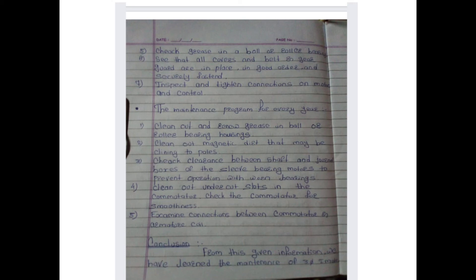The maintenance program for every year includes: first, clean out and renew grease in ball or roller bearing housing; second, clean out magnetic dirt that may be clinging to the poles; third, check clearance between shaft and journal boxes of sleeve bearing motors to prevent operation with worn bearings; fourth, clean out undercut slots in the commutator and check the commutator for smoothness; and fifth, examine connections between the commutator and armature coil.